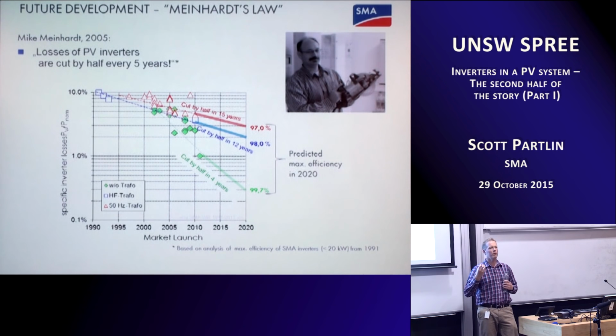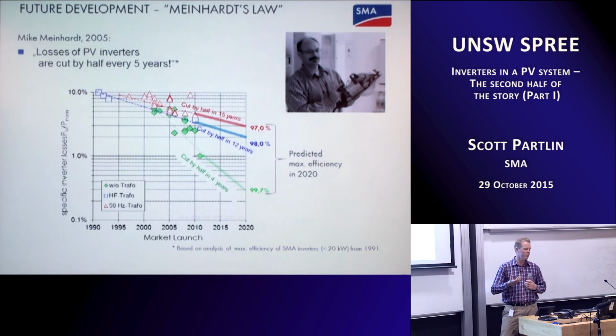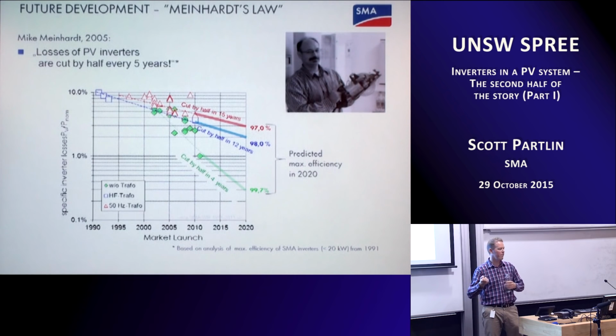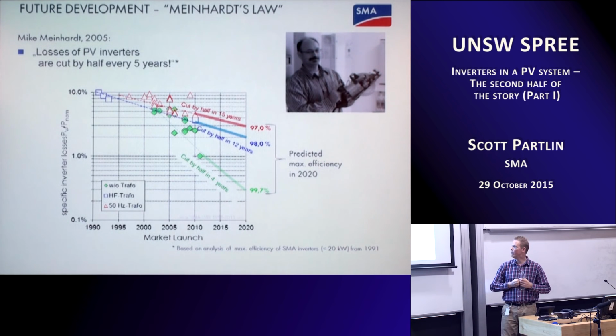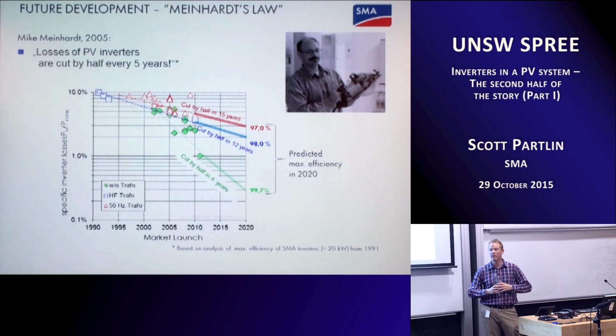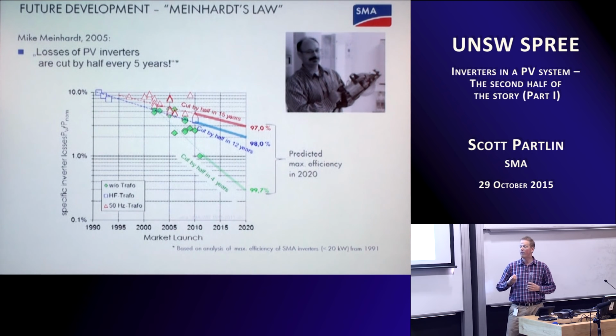With the first sort of technology, it took 15 years to cut the efficiency loss in half. For HF inverters, high frequency transformer-based inverters, which were produced at higher volumes, that efficiency loss was cut in half within 12 years. Transformerless inverters have seen the same cut in efficiency loss in 4 years. So the same as with PV, as the volumes have got larger and larger, the prices come down a lot faster, and the efficiency of inverters is improving at a faster rate with the uptake.